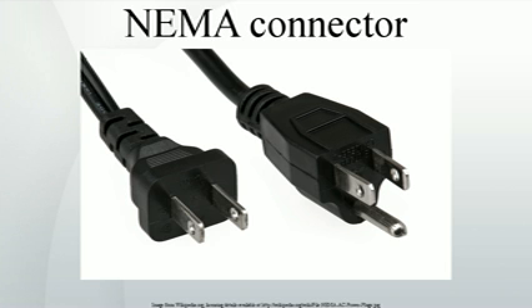Blue receptacles may indicate built-in surge suppressors. A red receptacle may indicate a special service outlet such as one connected to an emergency standby power source. At least one manufacturer makes a yellow receptacle, which identifies it as corrosion resistant. An orange receptacle is an isolated ground, IG, receptacle. A receptacle with a green dot is a so-called hospital-grade device. Such devices are tested to survive harder use than wiring devices intended for residential or commercial purposes.